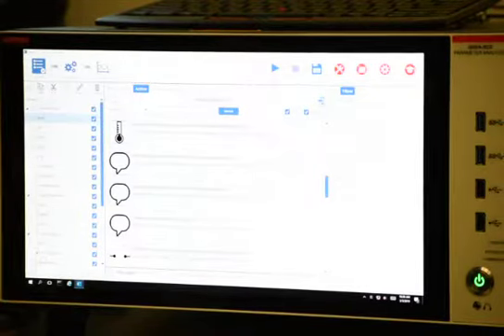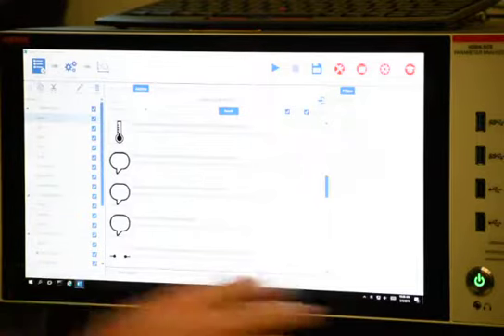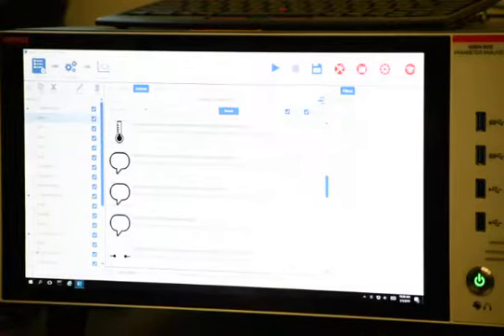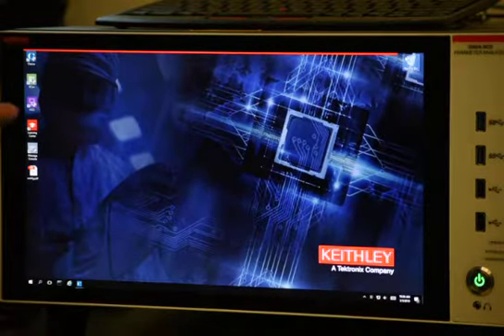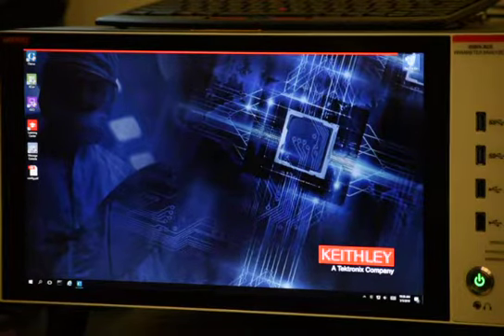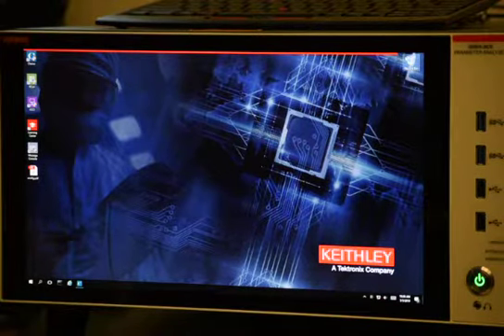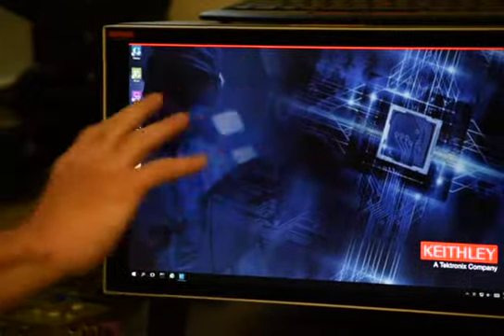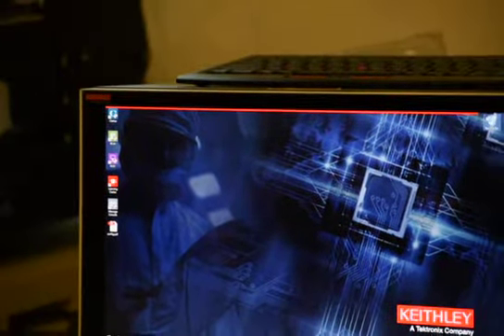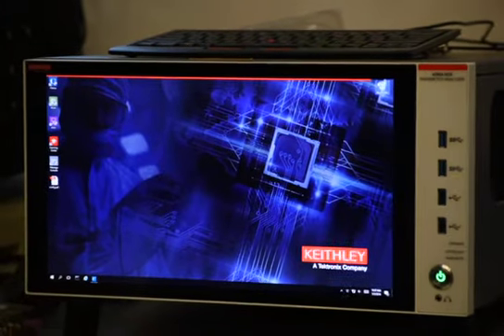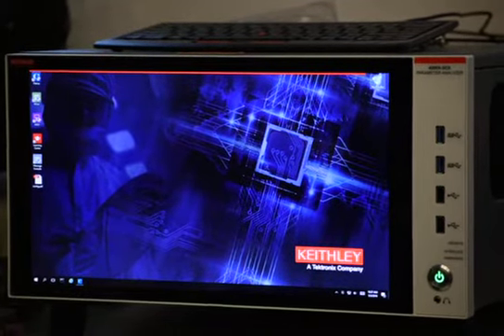If you want to, you can use this just like any other dumb instrument where you control it through LabVIEW or MATLAB from a laptop or another computer. You would have to turn around the GPIB bus, and that's what this KXCI is. It converts the GPIB to be a listener instead of a talker. So now it's just another dumb instrument, waiting for you to send it a command. You'll get a command line style interface, and when you send commands through your MATLAB or your LabVIEW, which can be on this machine, by the way, since it's a PC, then it will respond to those commands, and it'll act just like any other instrument would. Okay, so that's how you reverse the talker-listener roles of the machine.